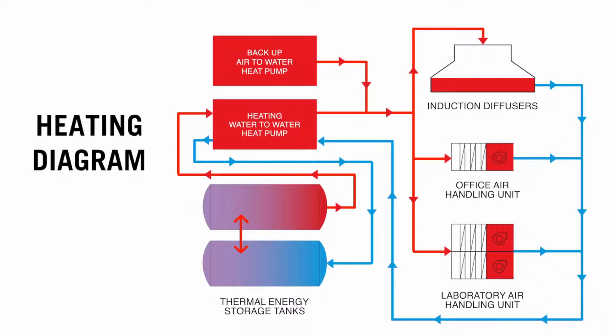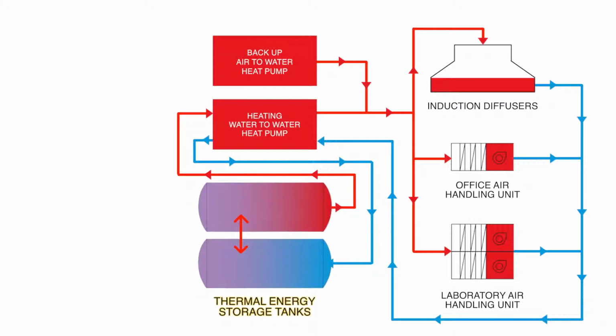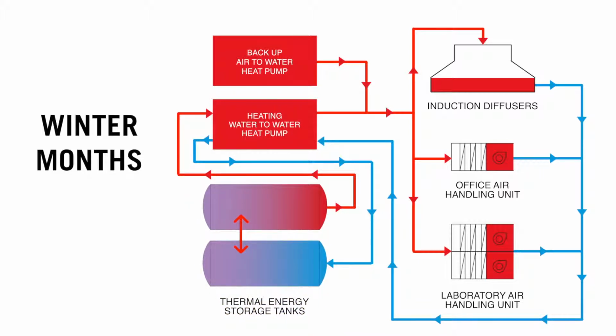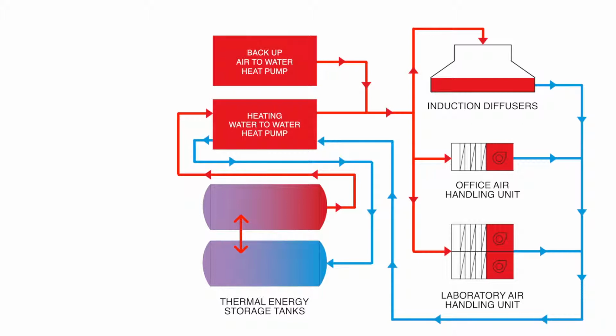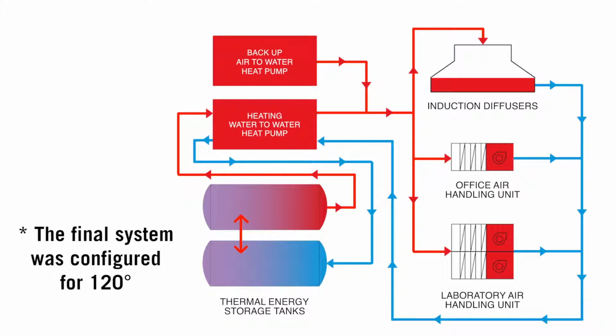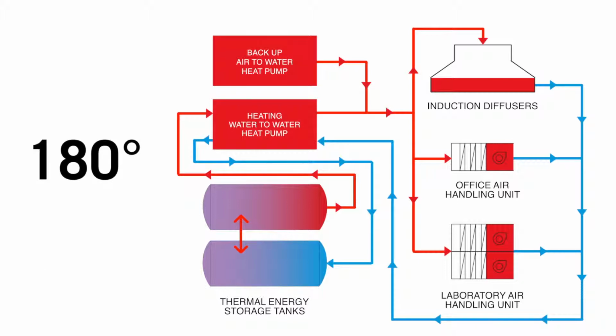Looking at the heating diagram, it's similar. We use the thermal storage tanks, but in the winter months when we need heat, and that's primarily in this climate when you need heat, we can take one of the tanks and run it as a warmer temperature tank, and we'll use the water-to-water heat pump to make that warm water. We set it up in a way that the heating is done with 100-degree Fahrenheit hot water instead of the typical 180-degree hot water system. If we had done that, the heat pump would have had to work a lot harder to make the hot water and used a lot more energy to do so.